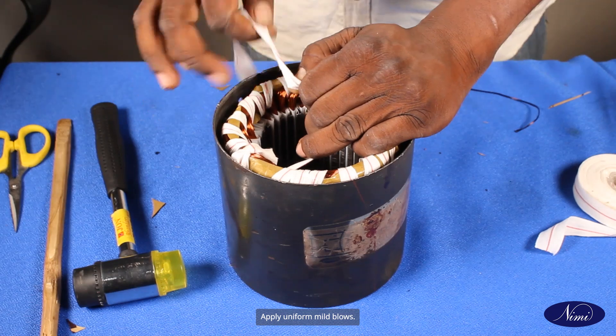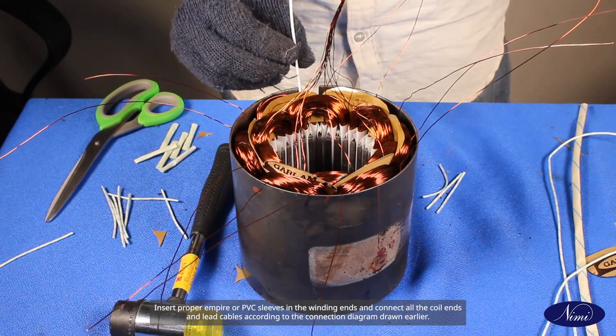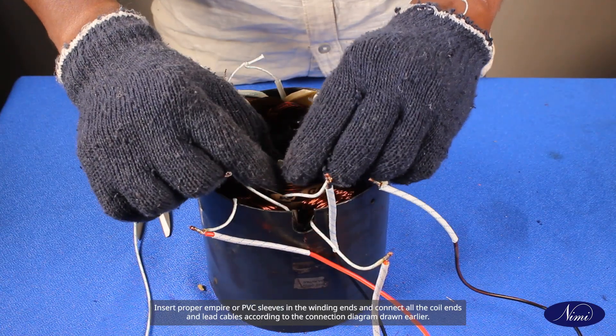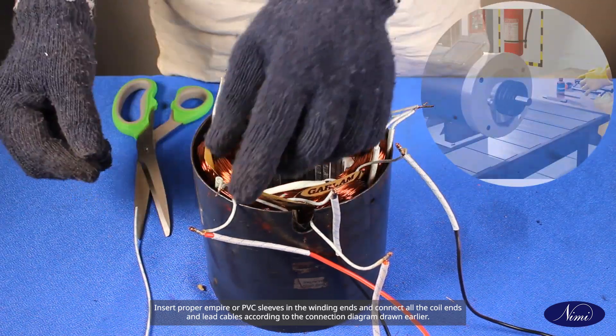Insert proper empire or PVC sleeves in the winding ends and connect all the coil ends and lead cables according to the connection diagram drawn earlier. Check the connection once again by comparing the group connection and developed diagram.